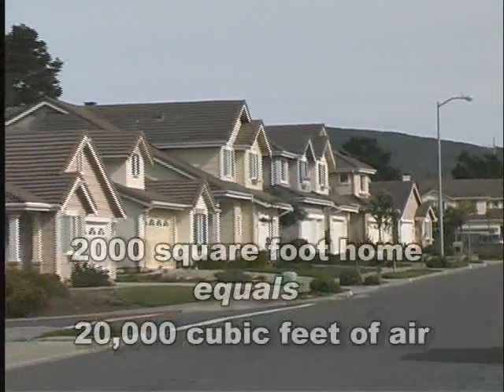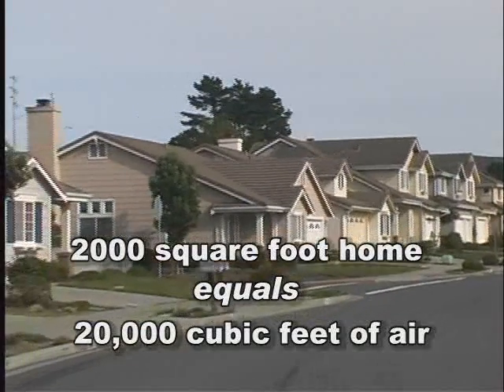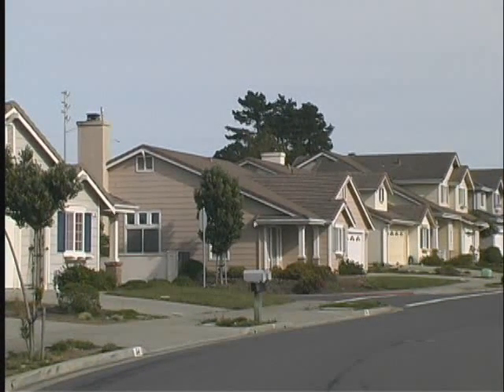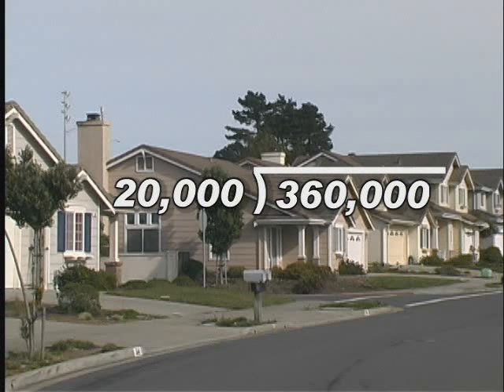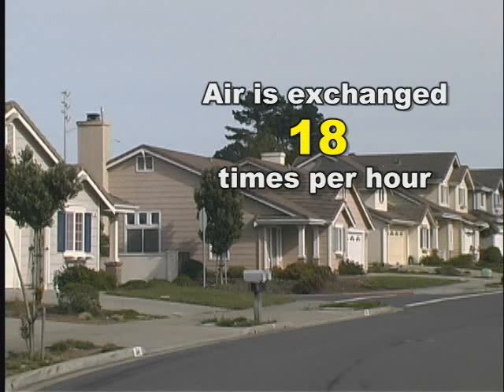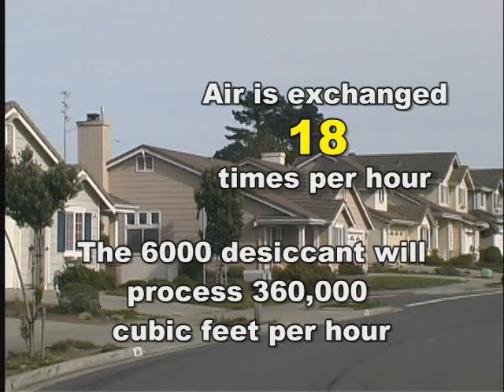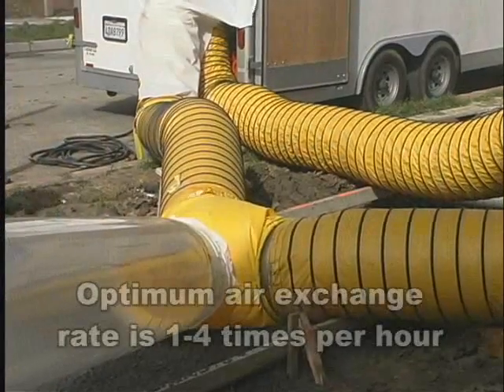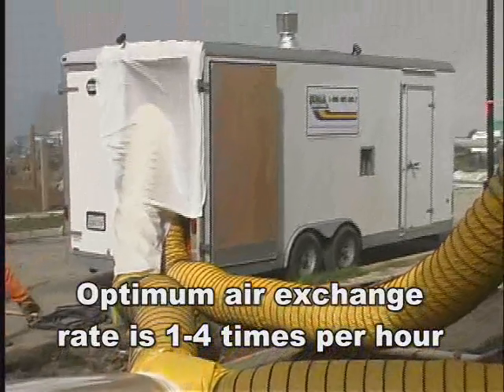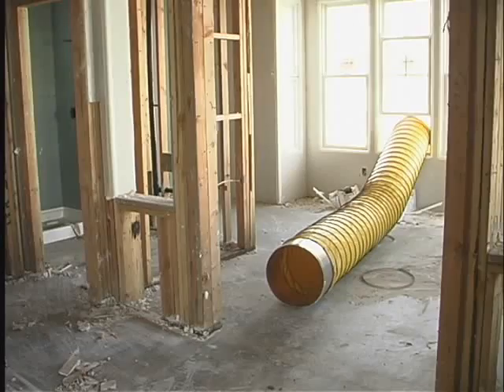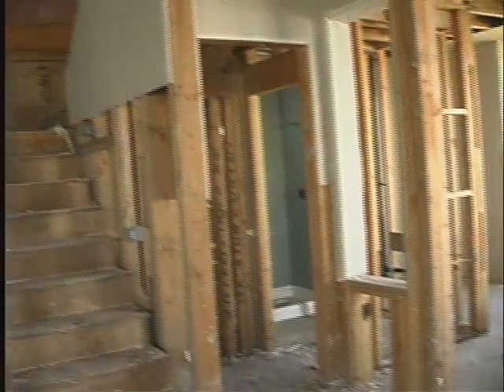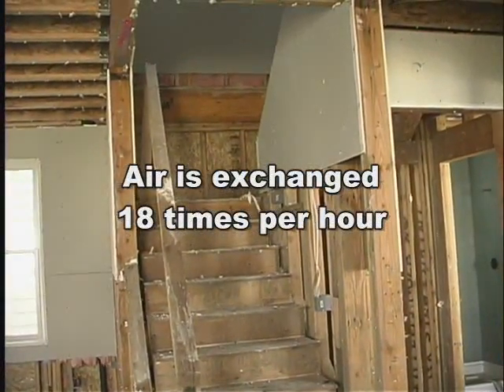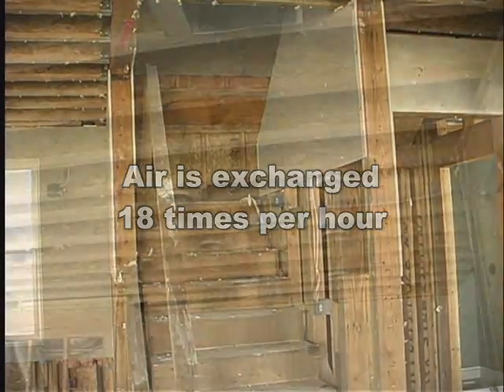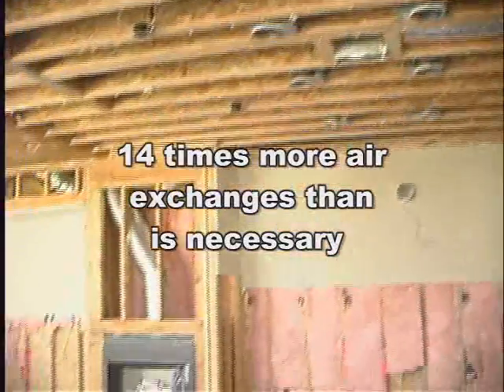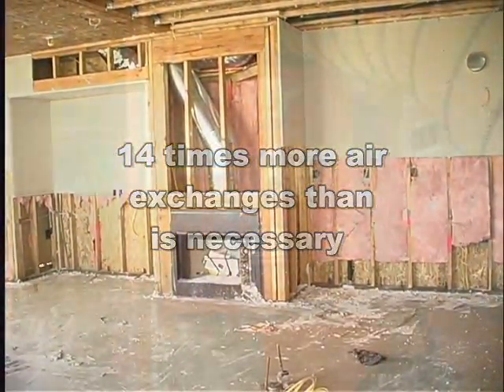We know that an average 2,000 square foot home contains approximately 20,000 cubic feet of airspace. Therefore, by applying simple division, we maintain that the air in the average 2,000 square foot home can be exchanged 18 times per hour. Remember, the 6,000 desiccant will process 360,000 cubic feet of air per hour. Our optimum air volume exchange rate target is 1 to 4 times per hour. This means that the total volume of air contained in a 2,000 square foot home is exchanged 18 times per hour. This is an extremely high value number that is 14 times more air exchanges than is necessary for drying the average 2,000 foot home.